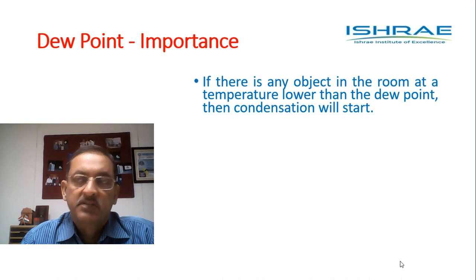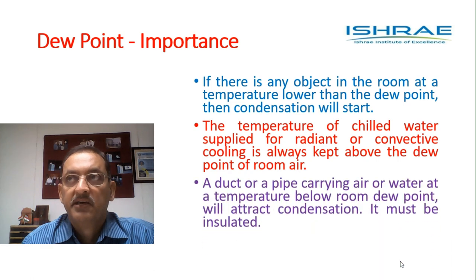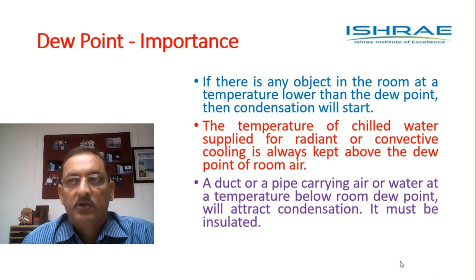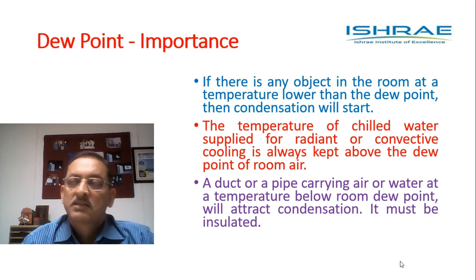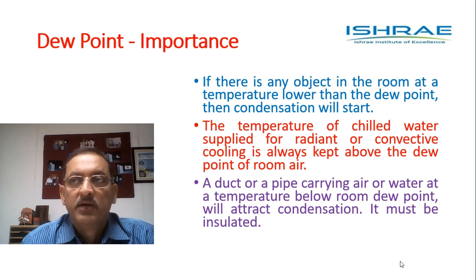If there is any object inside a room whose surface temperature is lower than the dew point, condensation will occur. It could be a duct carrying air or a pipe carrying water passing through a room. The key is not the inside temperature but the outside surface temperature — if the outside surface temperature is less than the dew point, condensation will take place. That is why it becomes necessary to have insulation around those pipes and ducts, so that the outer surface temperature is higher than the dew point.